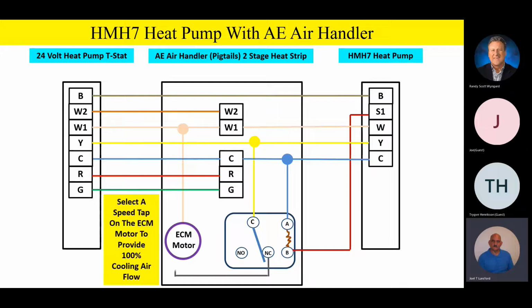On that little single pole double throw relay, the normally closed contact, there's going to be a wire hooked up from normally closed over to the ECM motor to provide 100% cooling airflow. So the contractor, when he sets this unit up, is going to have to measure his airflow, and he's going to set up that 100% airflow based on the tonnage of the outdoor unit. To give an example, let's say I have a 3-ton unit outside. That 100% airflow setting is going to need to be 1200 CFM on a 3-ton unit.